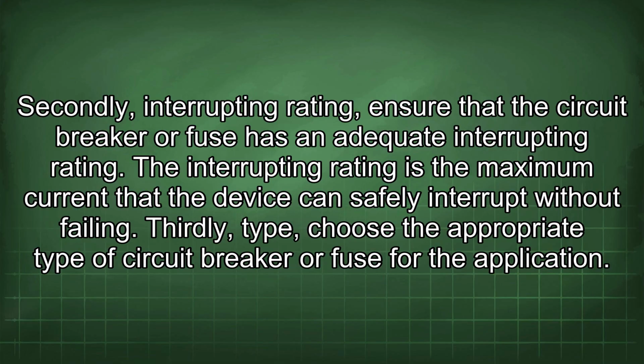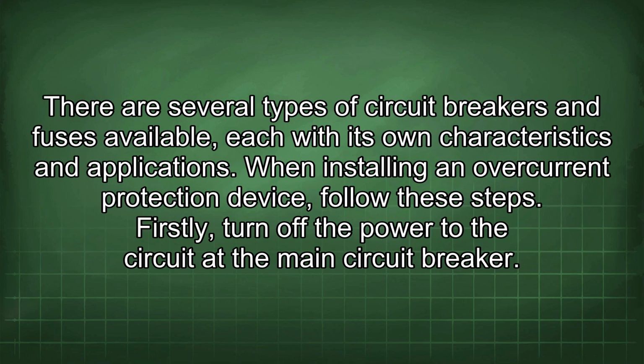Ensure that the circuit breaker or fuse has an adequate interrupting rating. The interrupting rating is the maximum current that the device can safely interrupt without failing. Thirdly, type. Choose the appropriate type of circuit breaker or fuse for the application. There are several types of circuit breakers and fuses available, each with its own characteristics and applications.